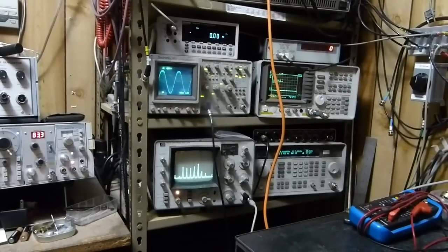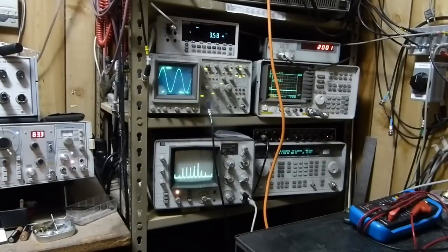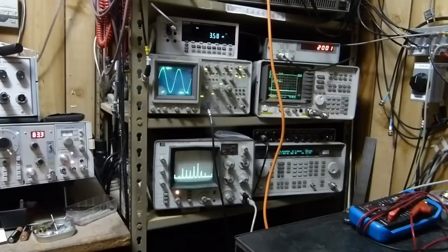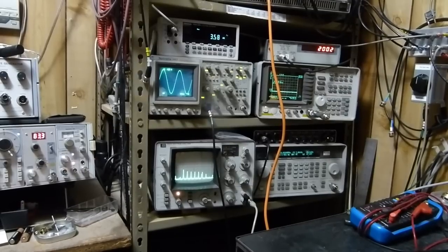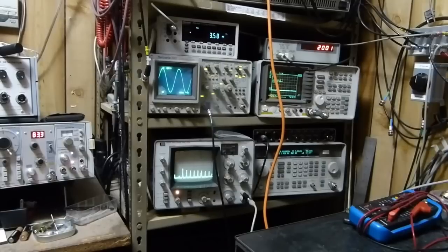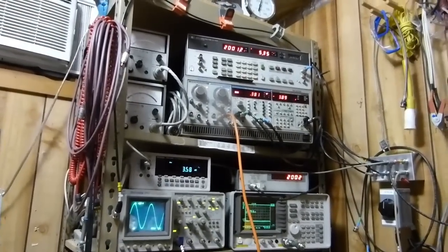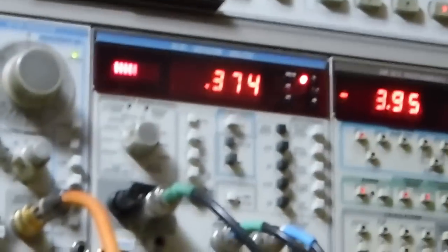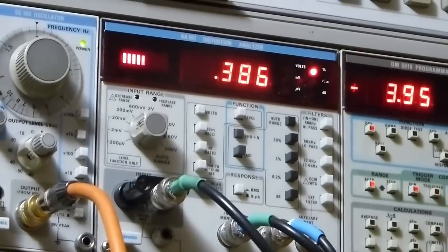Solid state. Boom. Power didn't change. Let's see if our harmonic profile changes. No, it actually went down a little bit. And look what our THD went to - it went from about 0.9, see that number right there, to 0.37, 0.38.